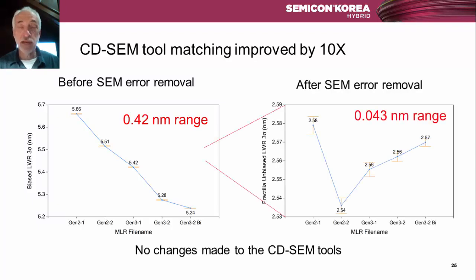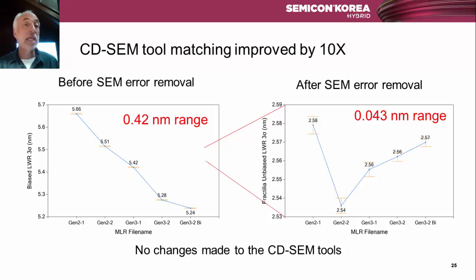What's the impact? The same wafer measured on six tools shows a range of 0.42 nm in the biased LWR. The variations in noise and systematic errors cause this large variation in measured LWR. But simply by taking those exact same images and measuring and subtracting out the errors, you can reduce that variability by a factor of 10 — with no changes made to the CD-SEM tools, only more careful image analysis. A 0.4 nm range — about 8% in the biased LWR — is too big to be useful for making decisions about which process is better; you'd end up making decisions based on which SEM the wafer was run on rather than which process produces lower roughness.